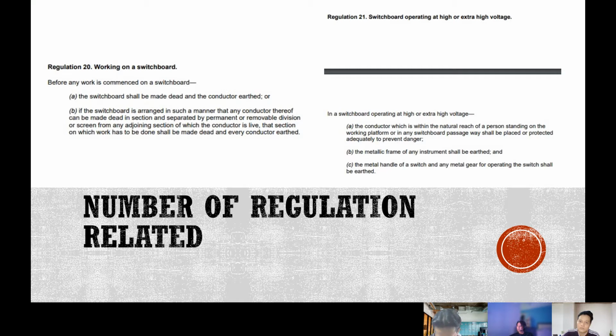A, the conductor which is within the natural reach of a person operating or standing on the working platform or in any switchboard shall be placed or protected adequately to prevent danger. B, the metallic frame of any instrument shall be earthed. And lastly, the metal handle of a switch and any metal gear for operating the switch shall be earthed.